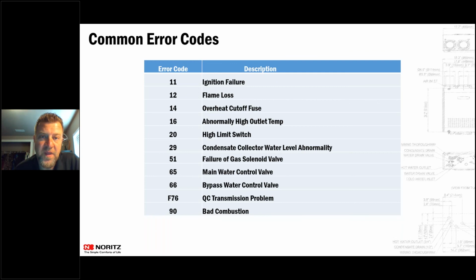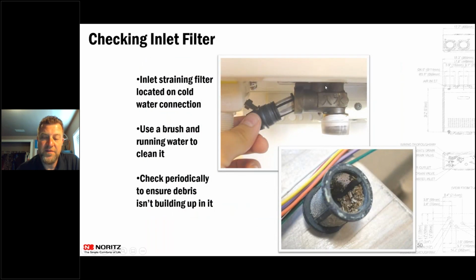I had one about a year and a half ago where they kept getting 90 codes, and the contractor couldn't figure it out. So I went out to the house, and they had painted the house about a week before and masked off the combustion air going into the house. It worked fine at a low BTU because it could pull enough combustion air from inside the house around the door, but when it got to high fire, it couldn't pull any combustion air, and so it would shut down. Those are the most common codes that we see out there.